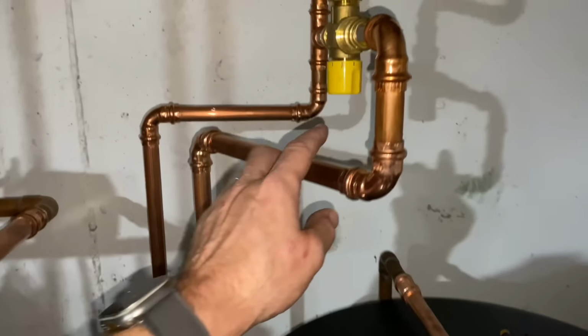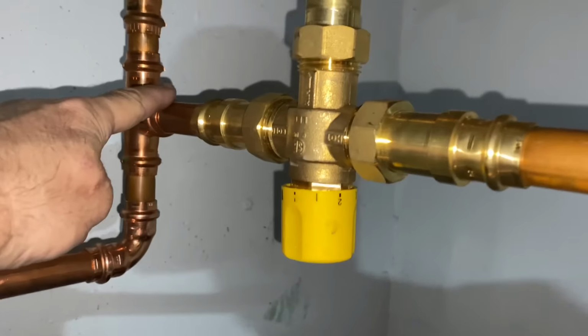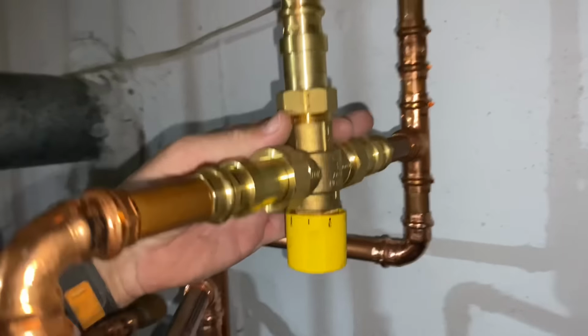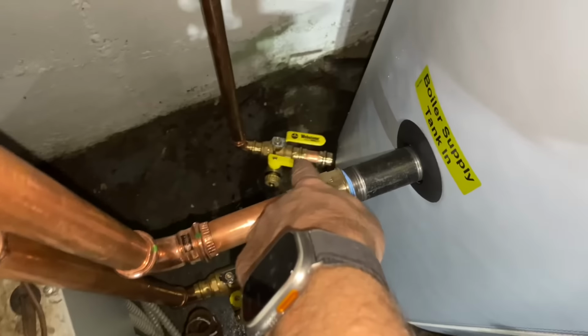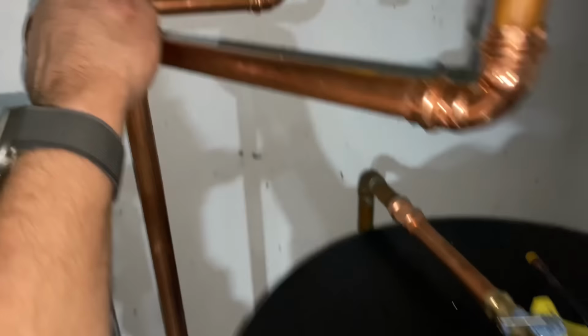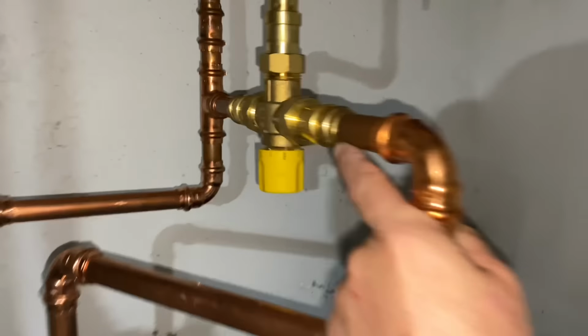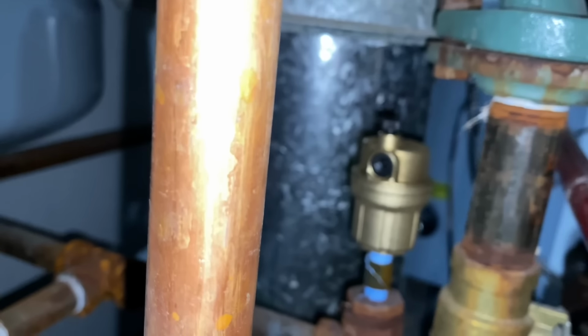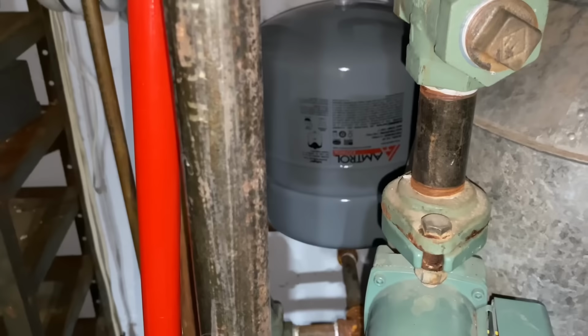My domestic cold water with my Webstone thermostatic mixing valve goes in to the bottom with the drain. And the hot to the mixing valve. And there's the mixed. On the boiler, we changed the tridicator gauge. Right there, it's new. Relief valve, right back there, dead center of the screen. Caleffi 1/8 automatic air vent with the check valve. And there's our Amtrol number 30 in the background.